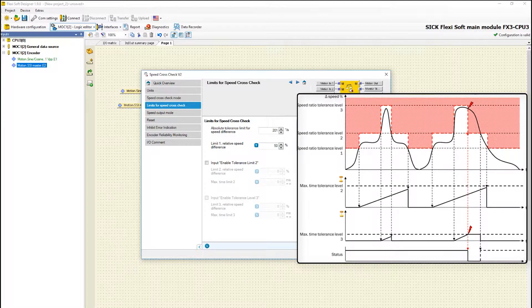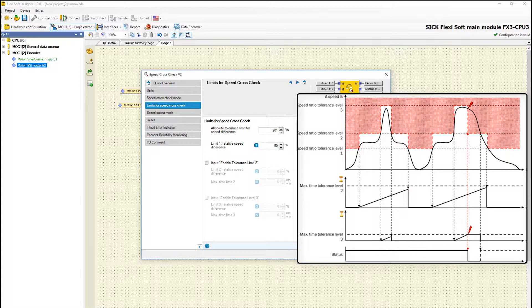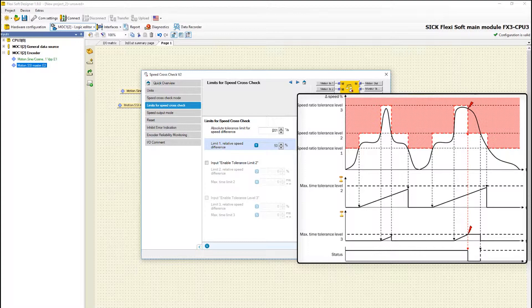The absolute speed difference will be checked first. Only if this value is exceeded the relative speed difference is evaluated. This helps to avoid tolerance errors which are caused by too small relative tolerance limits during low speeds.